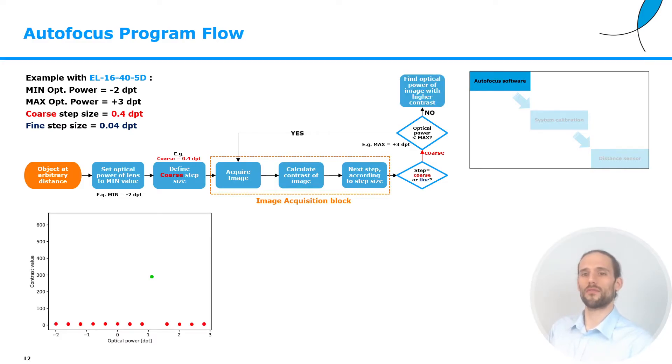When we have reached this optical power, we will find ourselves in a situation like depicted in the bottom line. We will have scanned over the whole optical power range of the lens, and we will acquire all the images. And one of these images will have the highest contrast of them all. At this point, we will basically define a smaller interval around this point, this optical power point. We will define a fine step size, which could be, for example, 0.04 diopters, so 10 times less than the coarse step size. Then we will set the optical power to the minimum of this just defined interval.